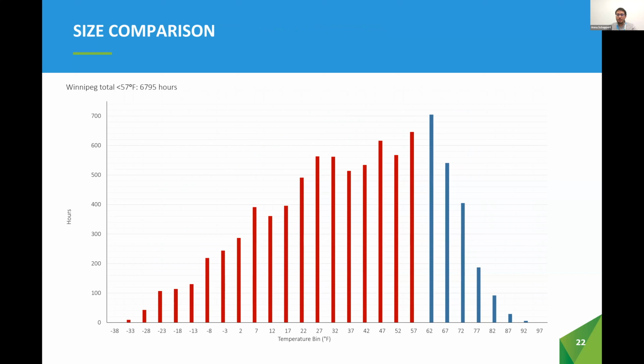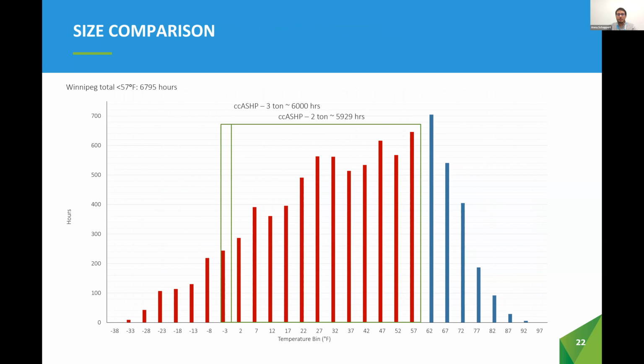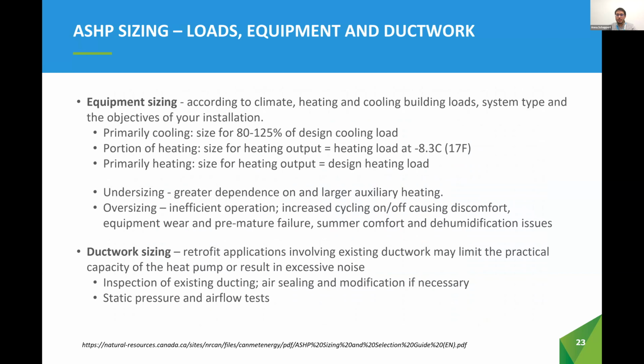While it may be advantageous to install the larger 4 ton unit for this home, as it would meet the vast majority of heating season hours, there are implications to oversizing a heat pump in such a way. Air source heat pumps should be sized based on the loads and in the context of the application goals. Some common approaches are to size for cooling, or to size for a portion of the heating, or to size for a majority of the heating. Undersizing will create greater dependence on, as well as a larger need for auxiliary heating to meet the peak demand, while oversizing will cause inefficient operation due to increased cycling on and off. This can cause thermal discomfort, dehumidification issues, and excessive equipment wear, leading to premature failure.